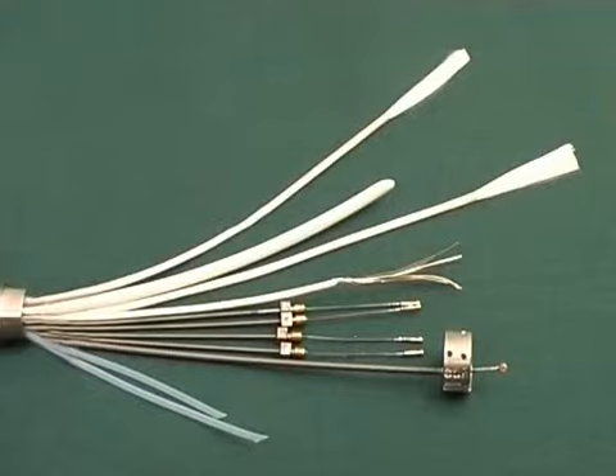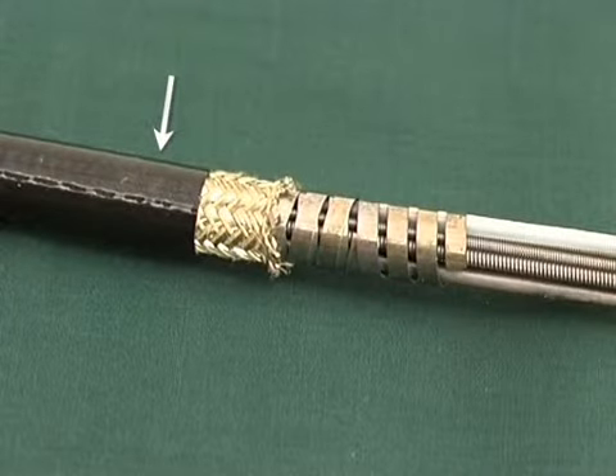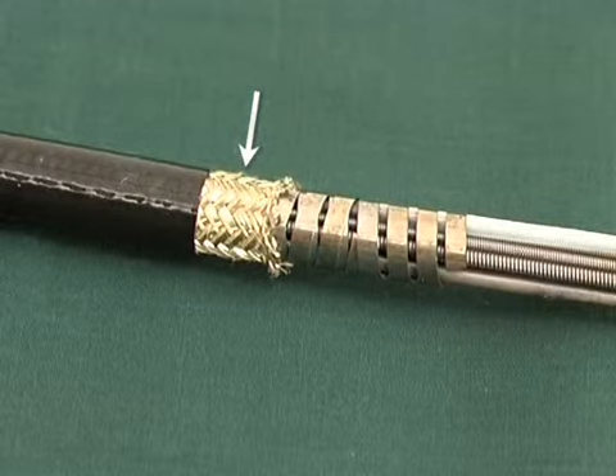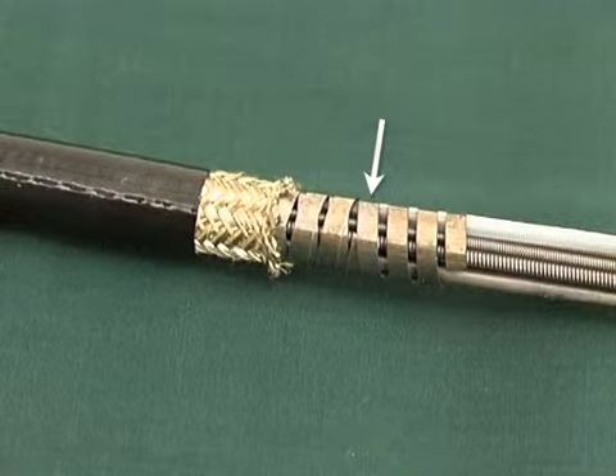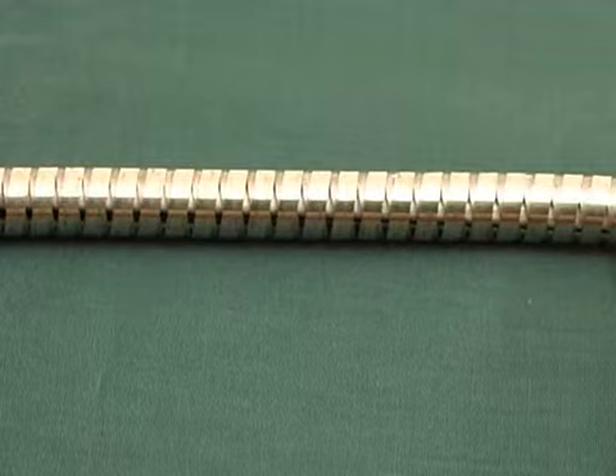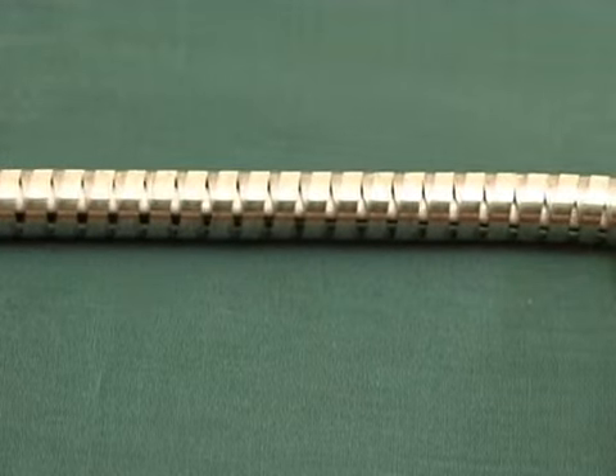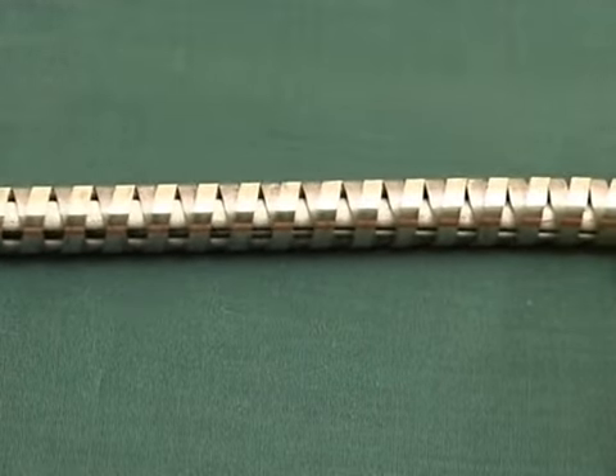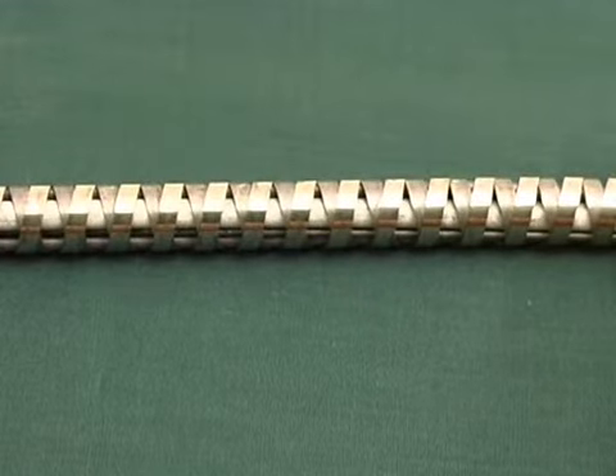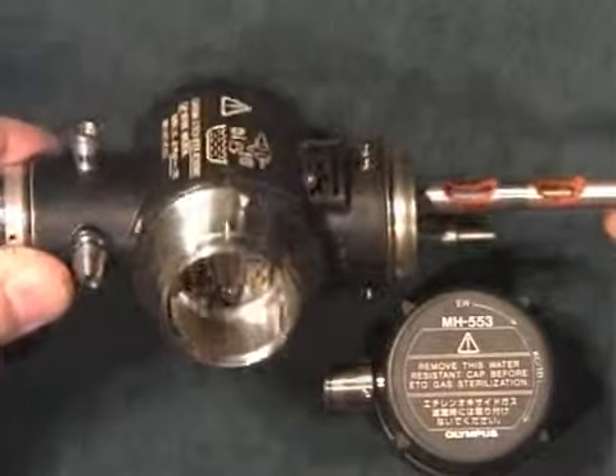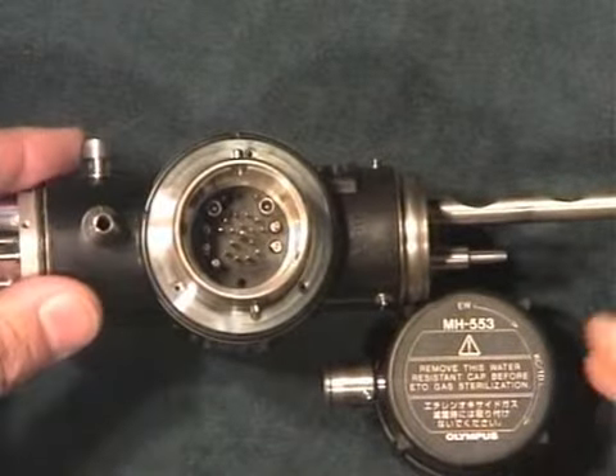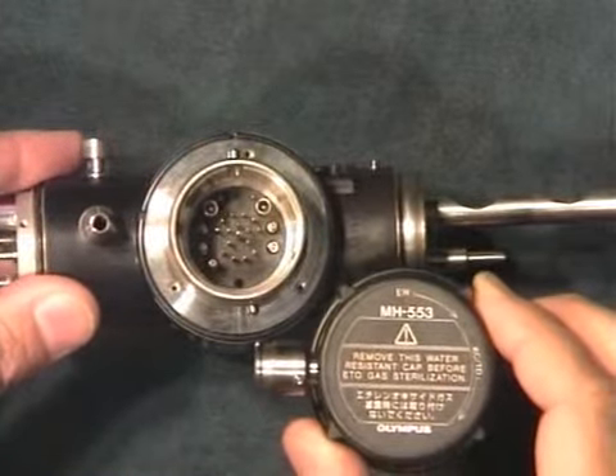These components need to be correctly ordered and lubricated to ensure that they move freely. The outer waterproof plastic layer covers a stainless steel braid. But critically, inside this, there are 2 phosphor bronze spirals, one clockwise, the other counterclockwise, which together give the shaft its torque stability. The components running through it terminate at the light guide plug with its waterproof cleaning cap.